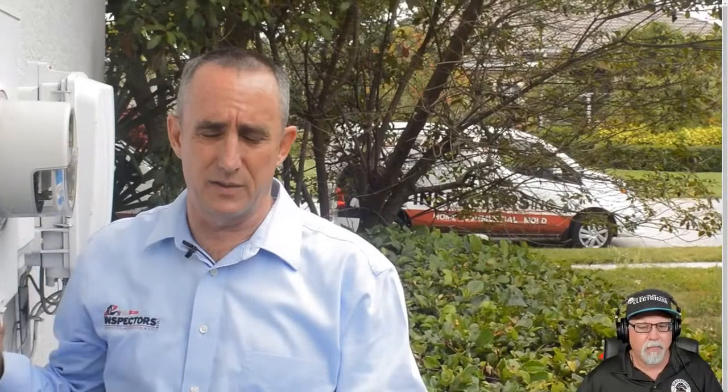I could supplement it with ground rods. I could supplement it with a Ufer. I could supplement it with pipe or plate electrodes. I have options. But the way he states it is incorrect. It's not an "and/or" with this. If you do have a water pipe ground like he says, then you're going to have to supplement it. There's no way around that, okay? That's a pretty good idea.